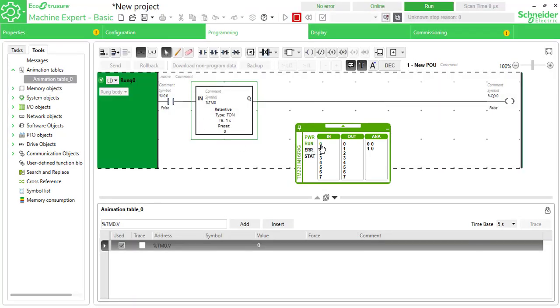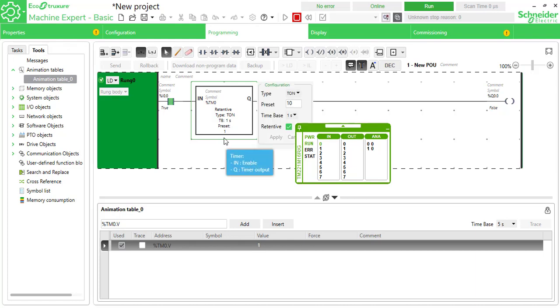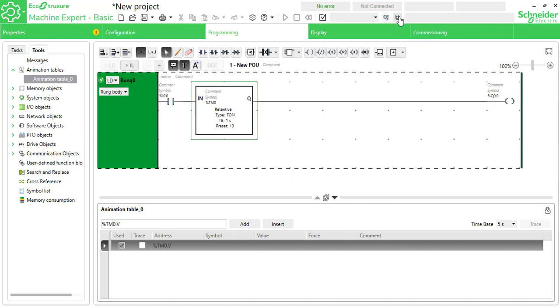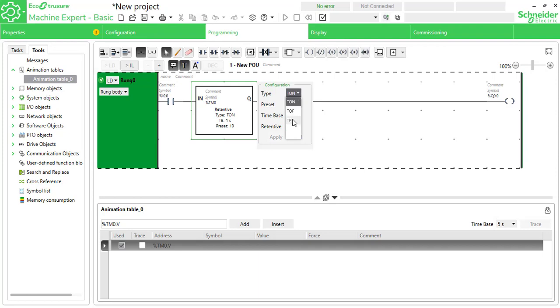Enable the contact and the timer runs — one, two... Press the off button during runtime and you can see the value prevails at the current state. Turn it on again and it runs from the current state. That is retention — even if there is a power failure, retentive timers won't lose their value.